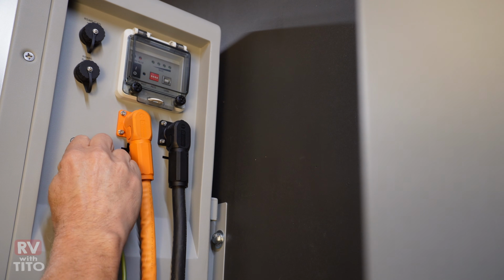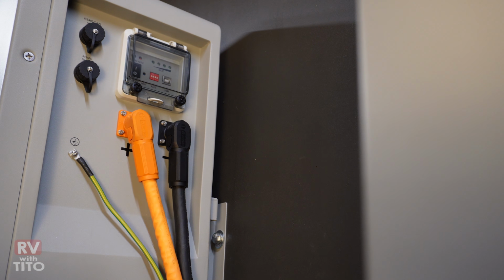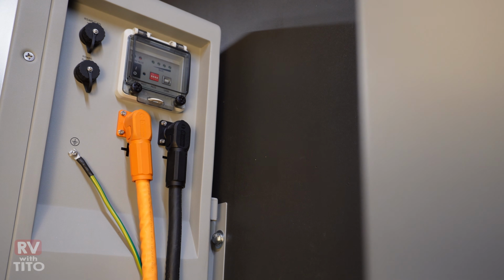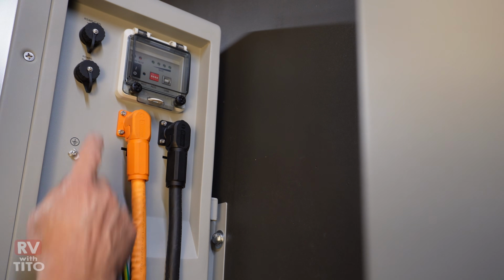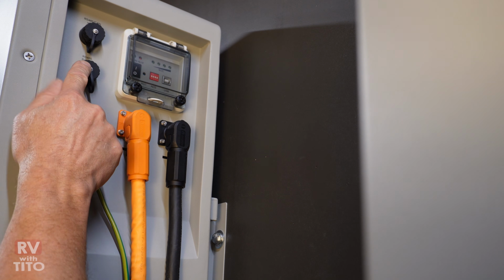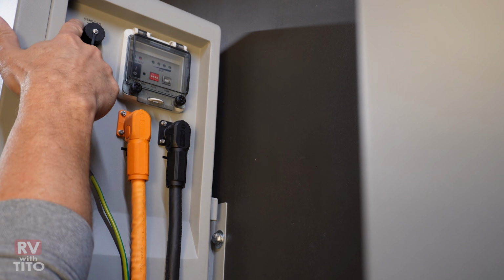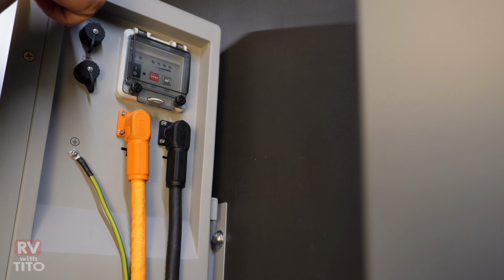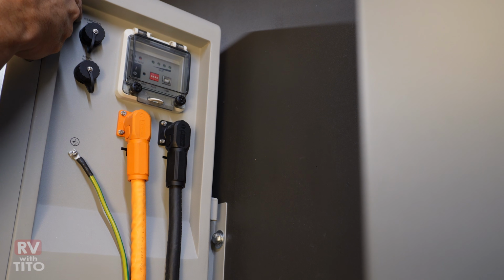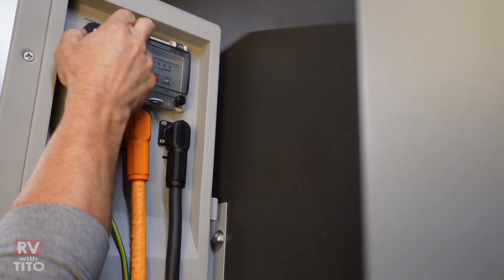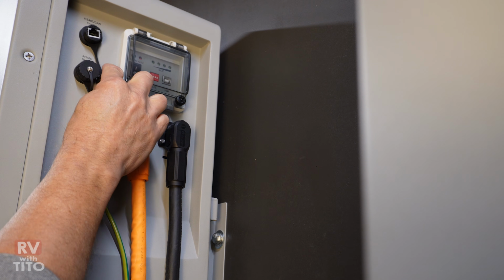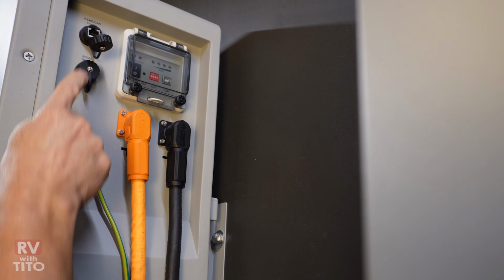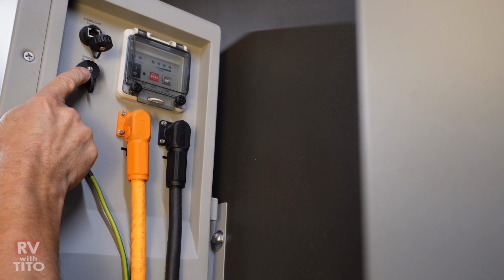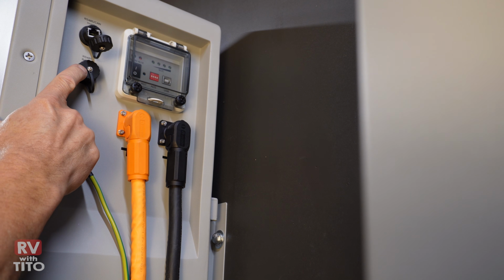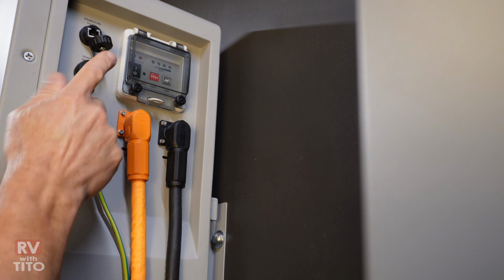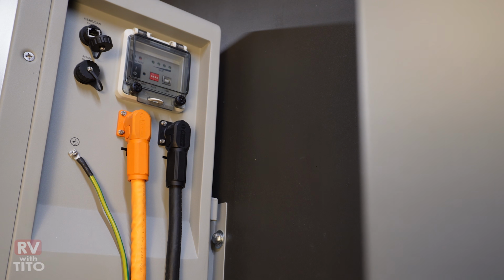There we go, I'll slide that behind here and route it to the inverter. Now we've got two communications ports here. This is the RS-485 and CAN port, with the word inverter underneath it, so that's what we're going to use for our communication cable. If we're using a secondary cable to connect to another battery, we'd use this one here, and there's one on the other side too, which I'll show you.